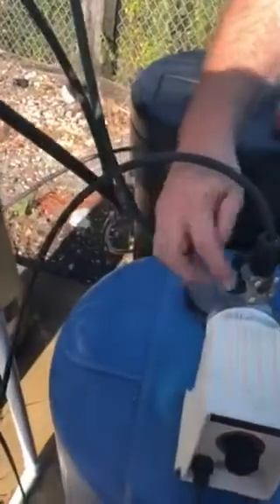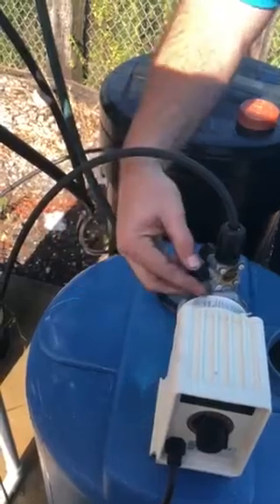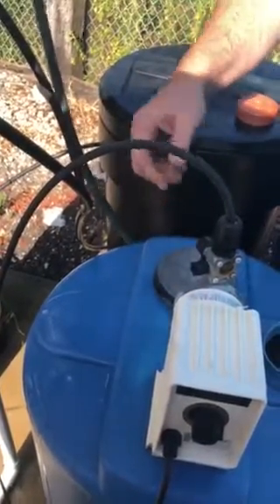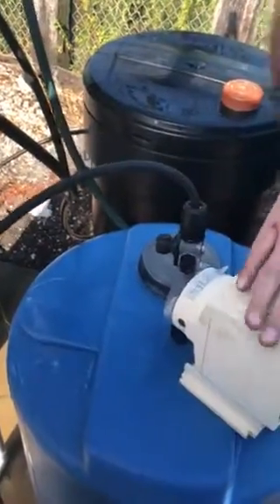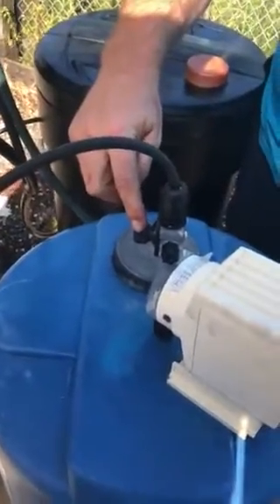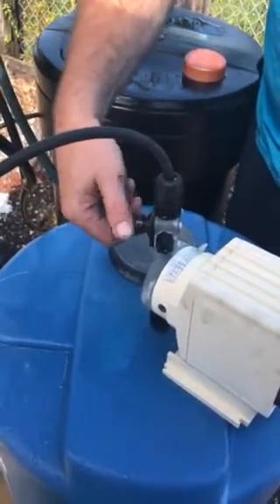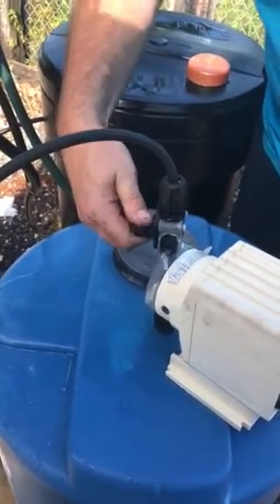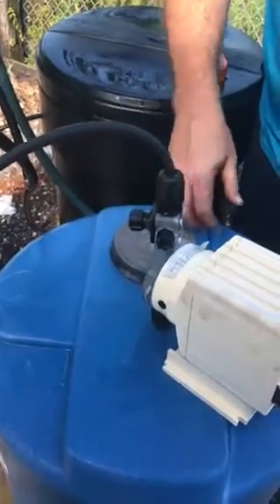Now, there are two places on the pump. There's this fitting right here — turning this does nothing; it's just if you wanted to extend a line. The fitting that matters most after you turn the pump on is right here. This is the priming knob. So I'm going to turn it a quarter turn — it doesn't matter which direction — basically to the left. And I'm going to start letting it prime itself.